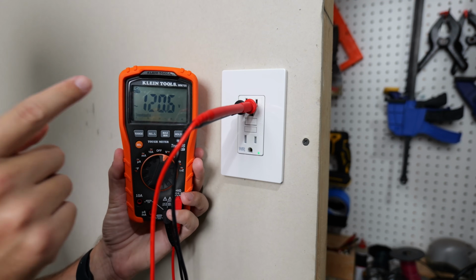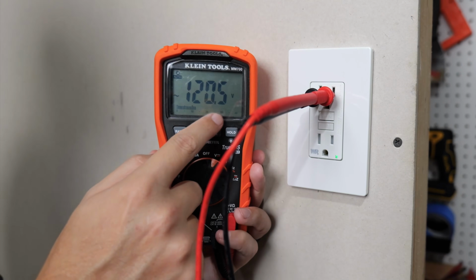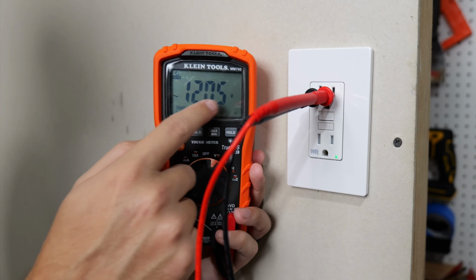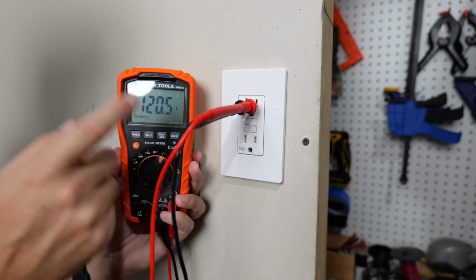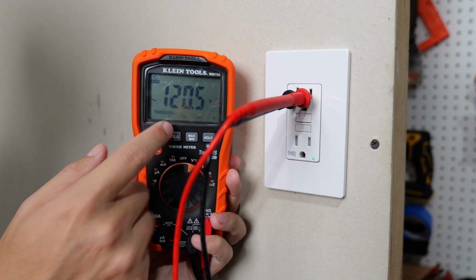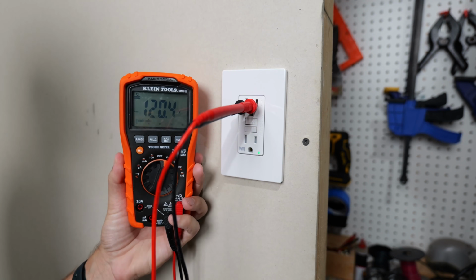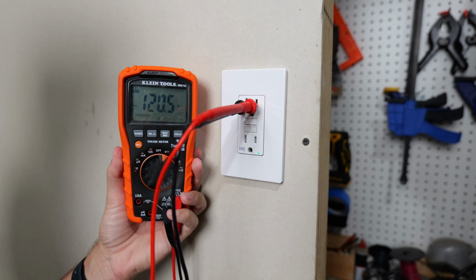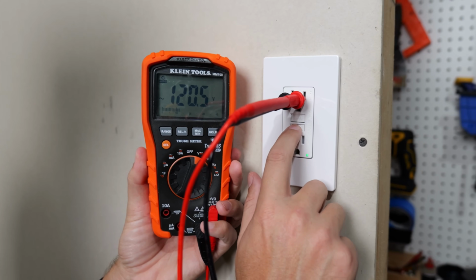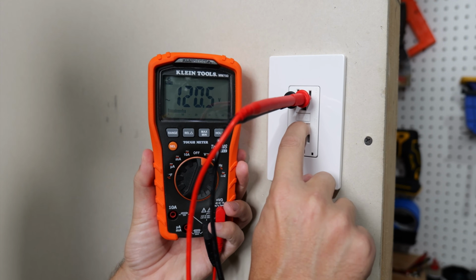If we were going to work on this receptacle, we'd want this reading to be 0, or just some very nominal voltage. Right now it's letting us know the power is still on, so it would not be safe to work on this, and we still need to find that circuit breaker. Once we find the circuit breaker and turn it off, which on this GFCI I'll simulate by just hitting the test button...